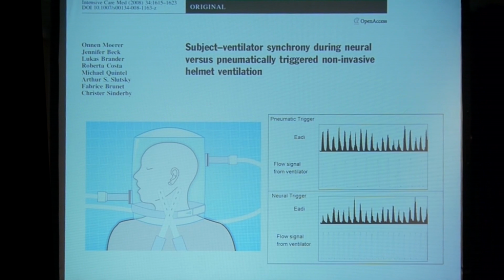And what we did was we also did pressure support with a neural trigger. So it's not NAVA, it's just pressure support. All we did was change the trigger mechanism. So here on the top tracings, you have your diaphragm electrical activity, and here on the bottom, you have the flow signal from the ventilator.